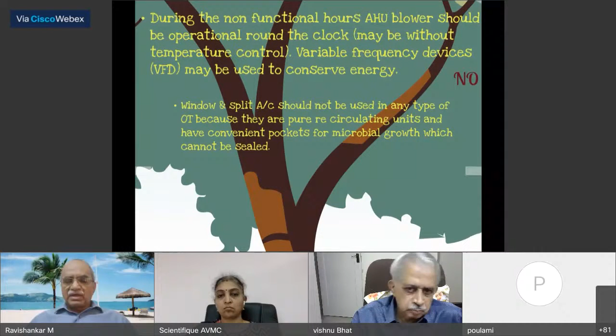So window and split AC should not be used in any type of operation theater because they are completely recirculating units. They don't take up any fresh air from outside, and they have convenient pockets for microbial growth, so you cannot clean them satisfactorily. So it is not recommended. Split AC or window AC is not at all recommended for operation theaters, and it should not be done.